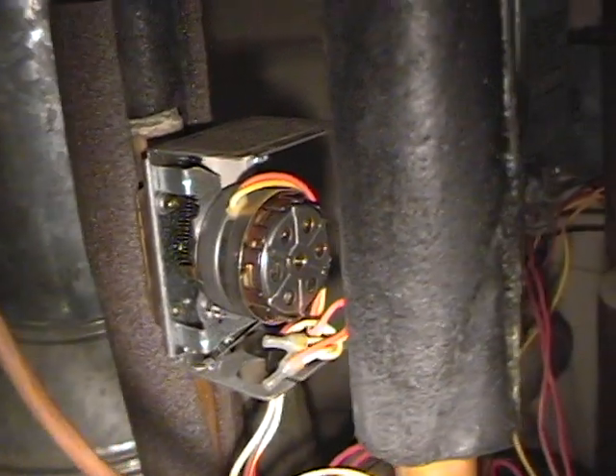So as a result, for the whole day I was at school, the boiler just kept running continuously the entire day, as did the air handler. So when I got home, the downstairs was about 80 degrees, and believe me, you could feel it when I opened the door. And I wondered what the hell was going on. And it turns out I shut off all the thermostats and nothing happened.